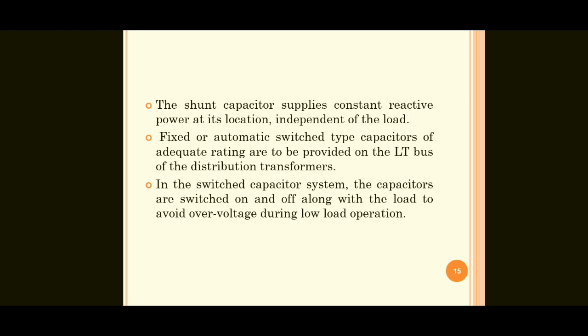So to avoid these over voltages, the capacitors are switched on and off along with the load. Because here, the second point is that the capacitors are provided on the LT side, meaning the secondary side, that is 400 volt. Loads are also placed on the secondary side because we step down 11 kV to 400, 400 to 230 volt. That is the rating.